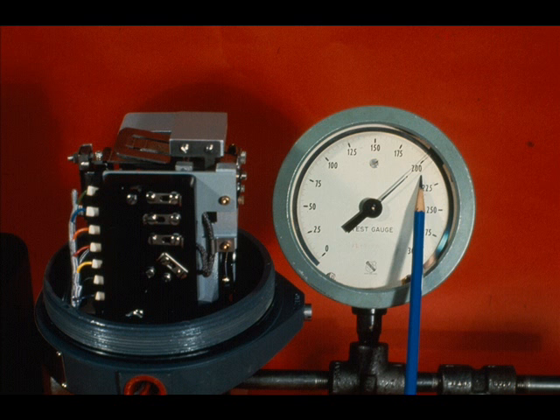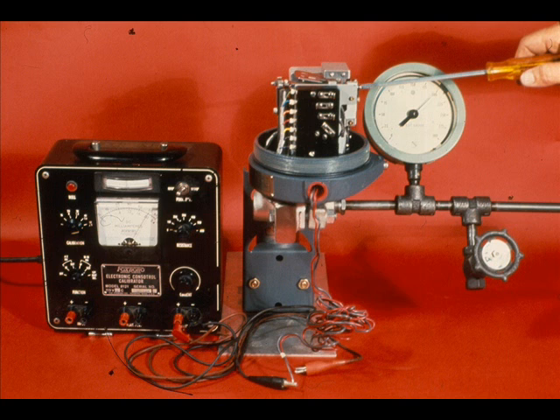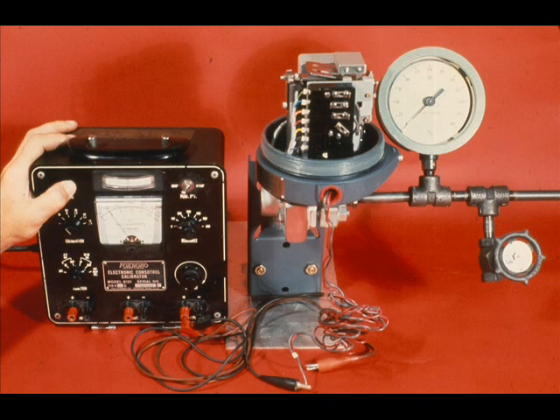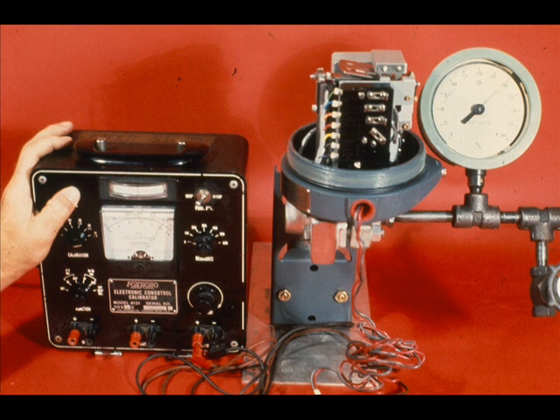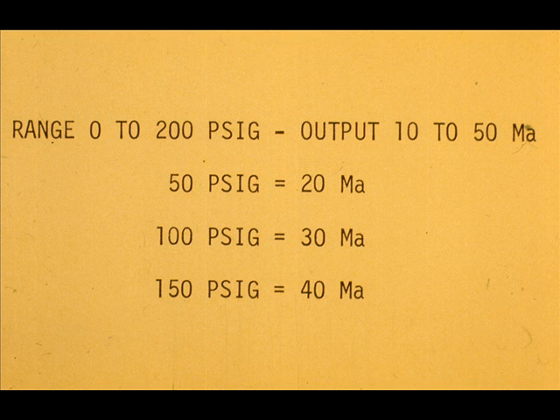With zero pressure input to the transmitter, adjust the transmitter zero for 10 milliamps output. With 200 PSIG input, adjust the span to give 50 milliamps output. Repeat the zero and the span adjustment until the zero to 200 PSIG calibration is correct.